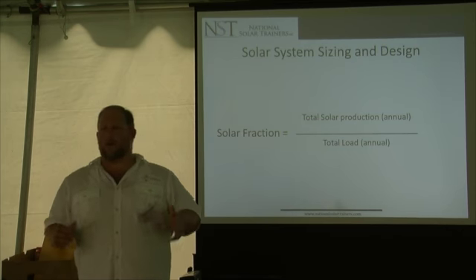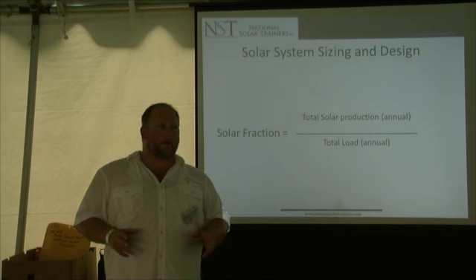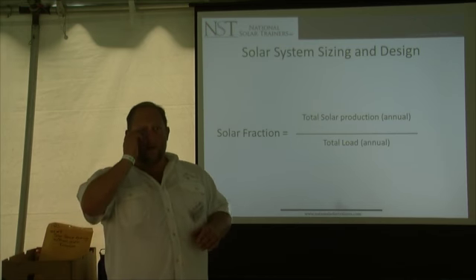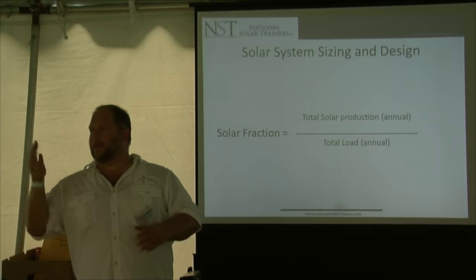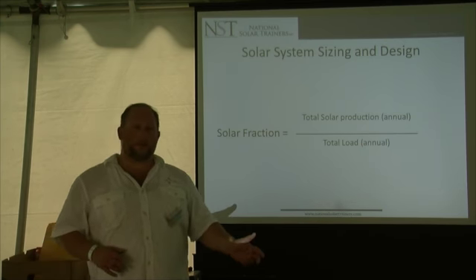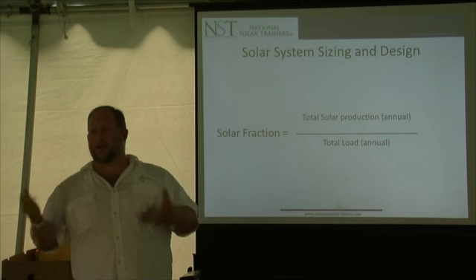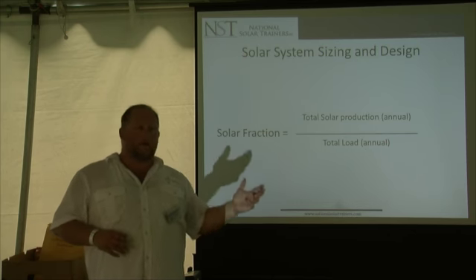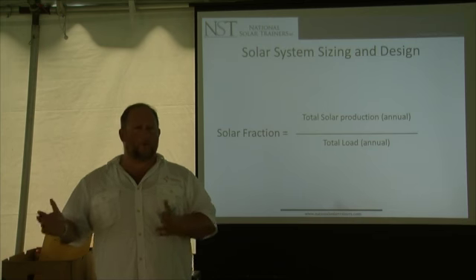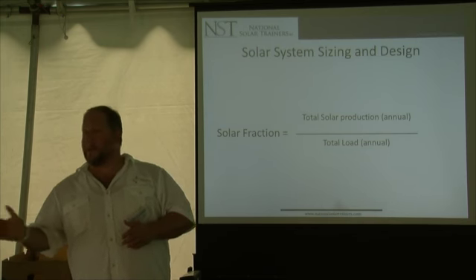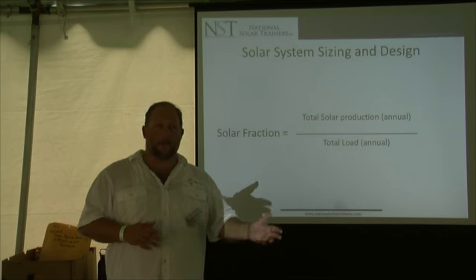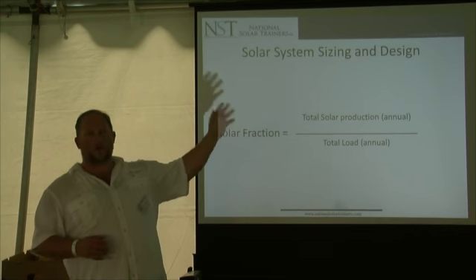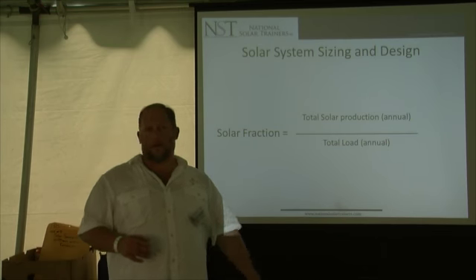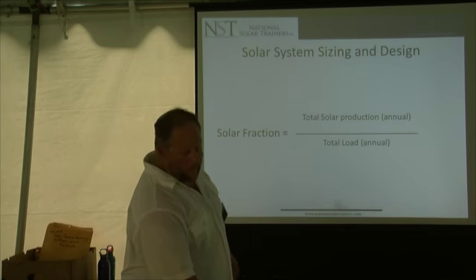Total solar fraction is important to consider because bigger is not better. There's a fine line between increased solar fraction and decreased efficiency. In this area, for domestic hot water, 45 to 55% is good, maybe 60%. Heating will be much less. Solar fraction is the total solar production divided by the total load.